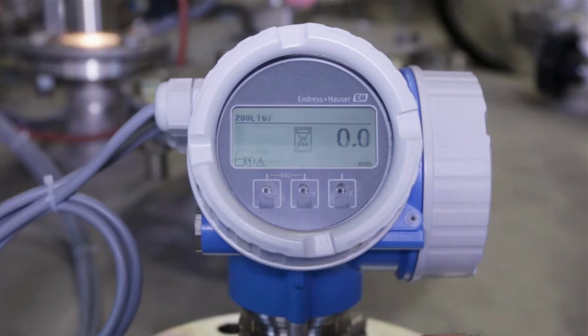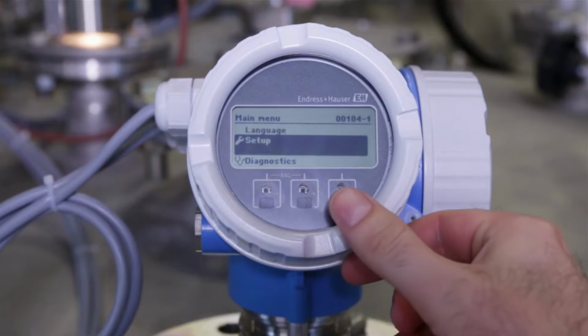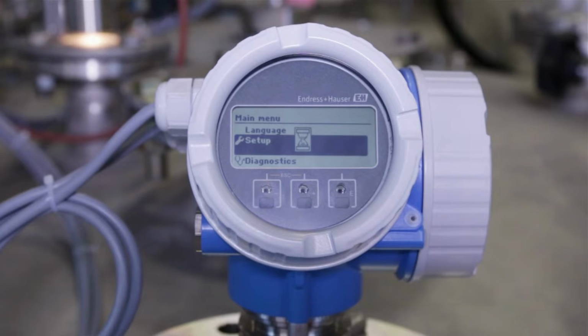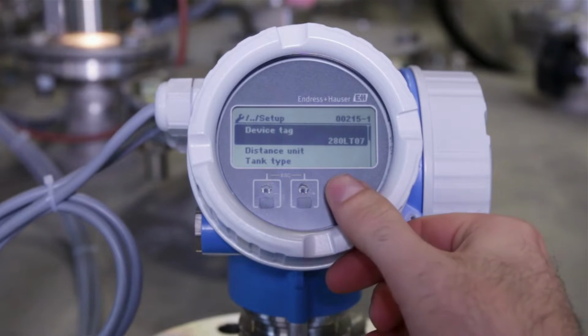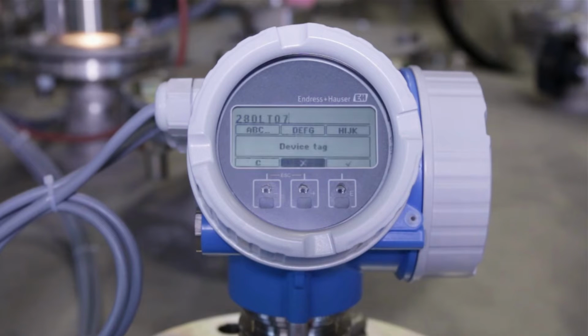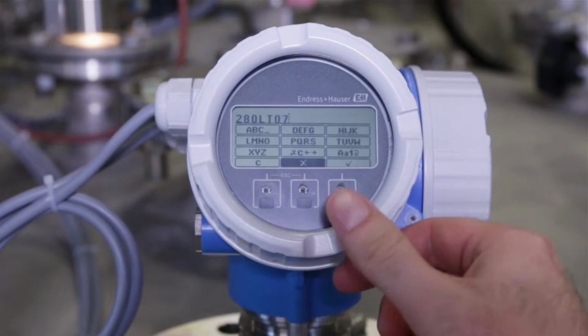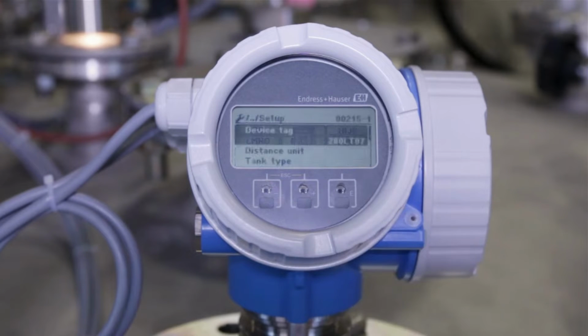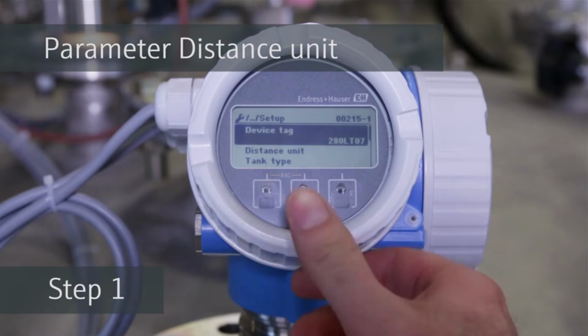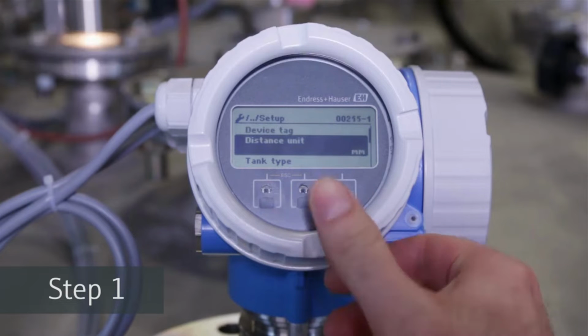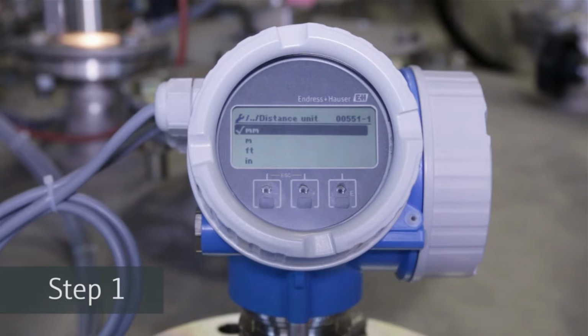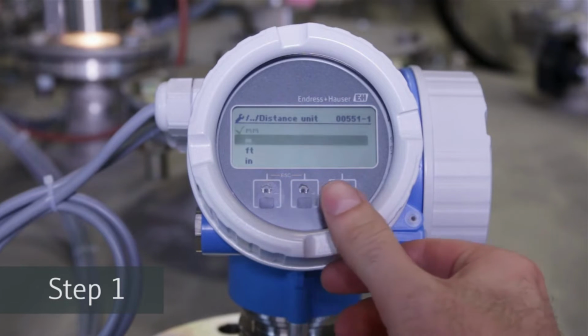First, open the main menu by pressing the E key and then selecting Setup. The Setup menu contains at the first position the parameter device tag. Here you can enter the name of the measuring point if required. Next, select the parameter distance unit. In our example, we select the unit meter.